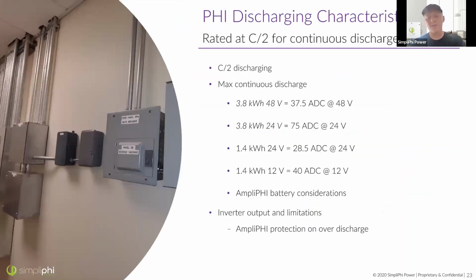Our discharge ratings are the same as our charge ratings, still C/2. So again, take that battery bank amp hour capacity and divide by 2. And this does scale up as you add batteries to the bank. So let's say you've got a 300 amp hour 48 volt bank that can discharge as a whole at 150 amps DC. So each battery is providing 37.5 amps.